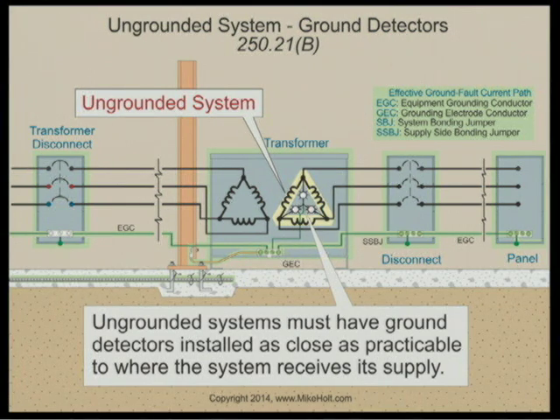But once you have a fault, once one phase goes to ground, the voltage between the other 2 phases changes relative to that reference point. Right now, the voltage from this point to the case is 120 because we put the light bulbs in there. Ah, so we're getting 120 on that one, because we put the light bulb there.